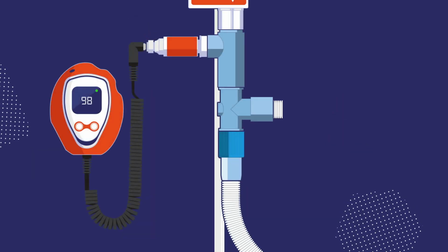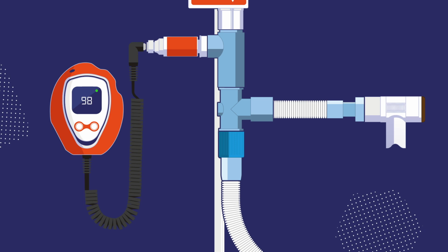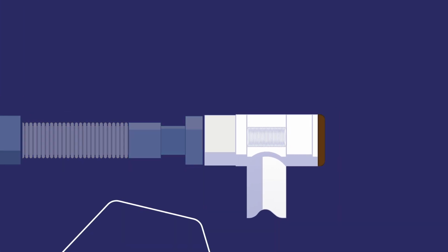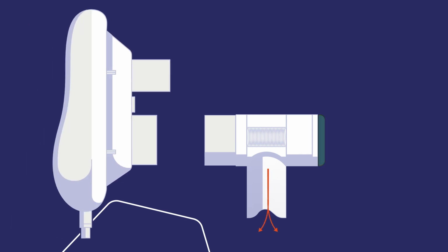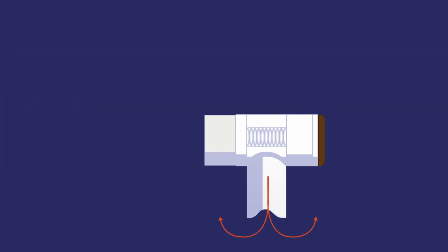If the flow generator requires the use of an external safety PEEP valve, make sure the valve is securely positioned at the end of the breathing circuit. The safety PEEP valve helps in the event where the PEEP valve that is attached to the face mask becomes occluded. Thus, any excess circuit pressure above the prescribed PEEP pressure will be relieved.